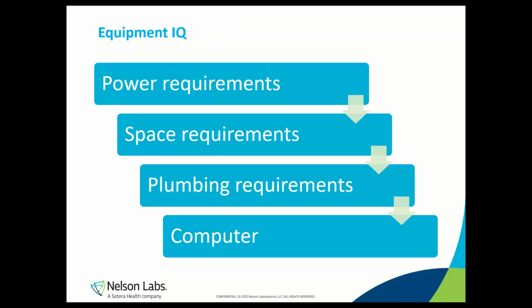The IQ, or installation qualification, is where we are documenting the equipment installation. This includes ensuring that all the utility requirements were met. So you need to ask questions like, what are the power requirements for the sealer? How much space does the sealer need for proper ventilation? Are there options like gas fill or vacuum draw that need to be installed or require special utilities? Does the sealer require emergency power backup?